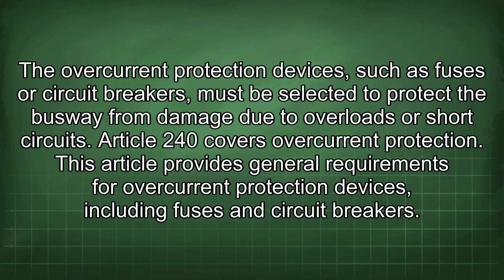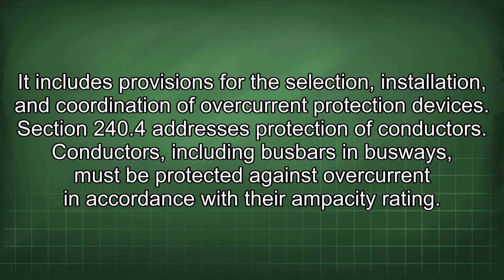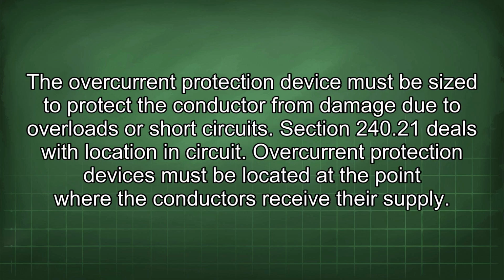Article 240 covers overcurrent protection. This article provides general requirements for overcurrent protection devices, including fuses and circuit breakers. It includes provisions for the selection, installation, and coordination of overcurrent protection devices. Section 240.4 addresses protection of conductors. Conductors, including busbars in busways, must be protected against overcurrent in accordance with their ampacity rating. The overcurrent protection device must be sized to protect the conductor from damage due to overloads or short circuits.